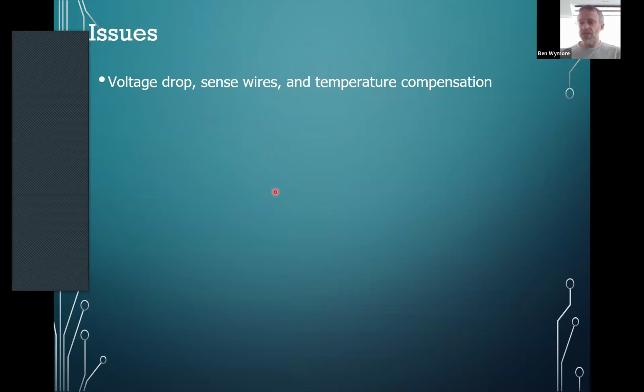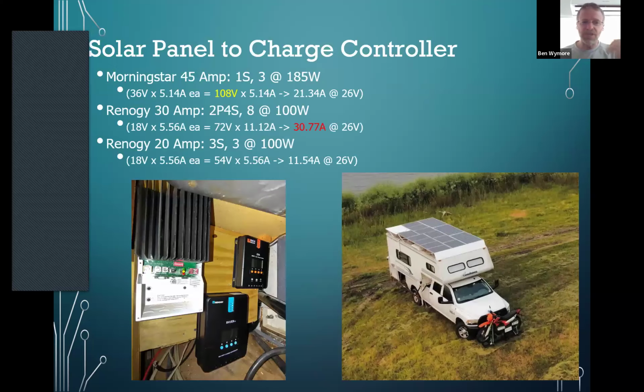The issue is the Morningstar, the commercial grade solar controller, has terminals for sense wires, but these Renogy ones do not. So there's no real way around it other than moving the Renogy controllers closer to the battery, using bigger wires, or going to a higher battery voltage so smaller wires would have less of an impact.